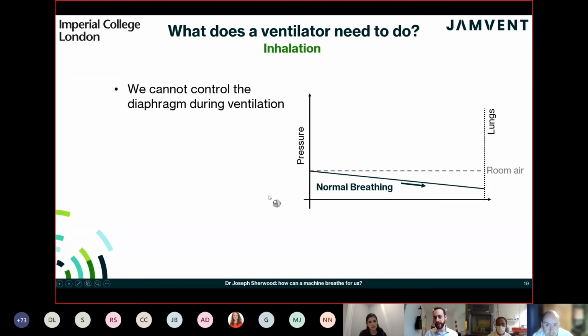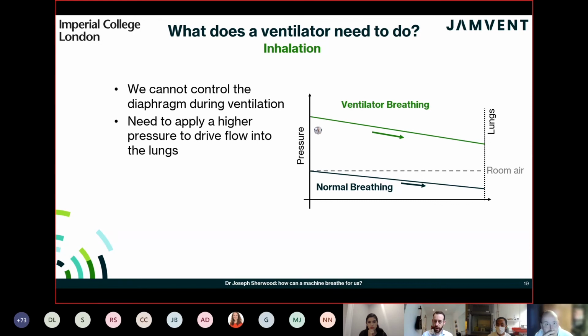So what about a ventilator? As you can see here, we've got a diagram of normal breathing. On the left-hand side, we've got the atmosphere, the reference pressure outside the lungs. And on the right-hand side, we're showing the pressure inside the lungs. We've just seen that you actually create a vacuum inside the lungs, and that draws fluid into the lungs. But we can't do that during ventilation because we can't control the diaphragm. So instead, what we have to do is apply a high pressure from the ventilator and use that to drive fluid into the lungs.